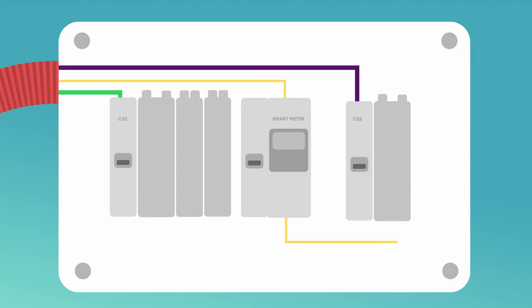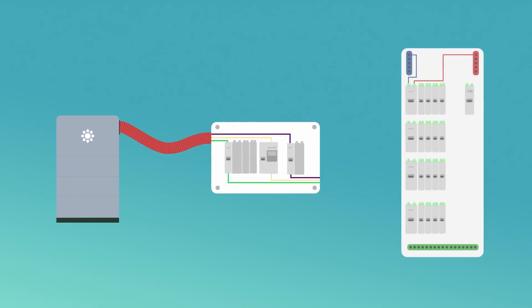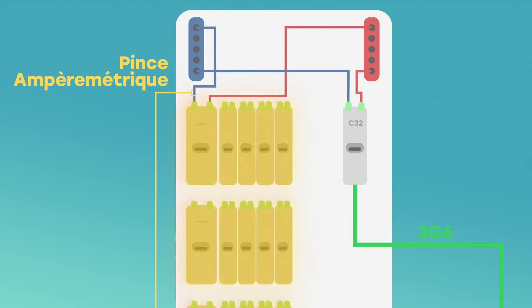From this smart meter, we come out with a ammeter clamp that will allow us to measure the house's consumption, and therefore know when the panels produce a surplus and when the battery should capture that surplus. We then come out of the safety box with two 3G6 cables and the ampere clamp cable connected to the smart meter. The ampere clamp is placed in the electrical panel around one of the main supply cables. In the panel, we connect the first 3G6 cable to a 32A circuit breaker and connect the circuit breaker to the phase distributor — this will let the battery power the whole house.